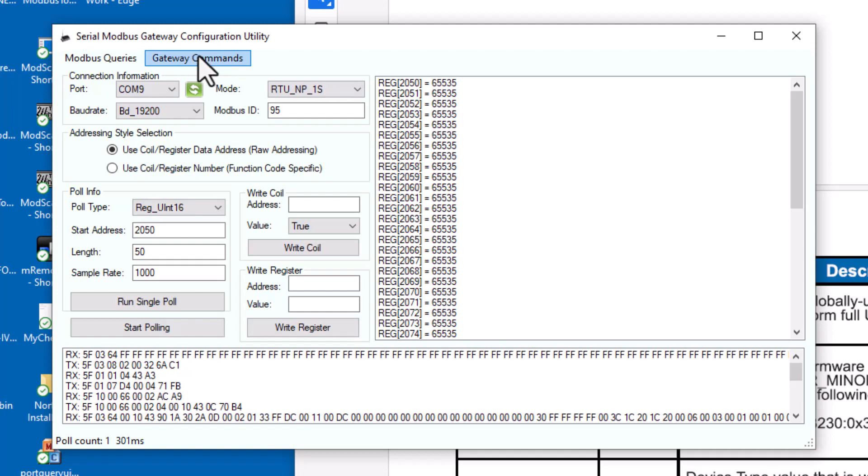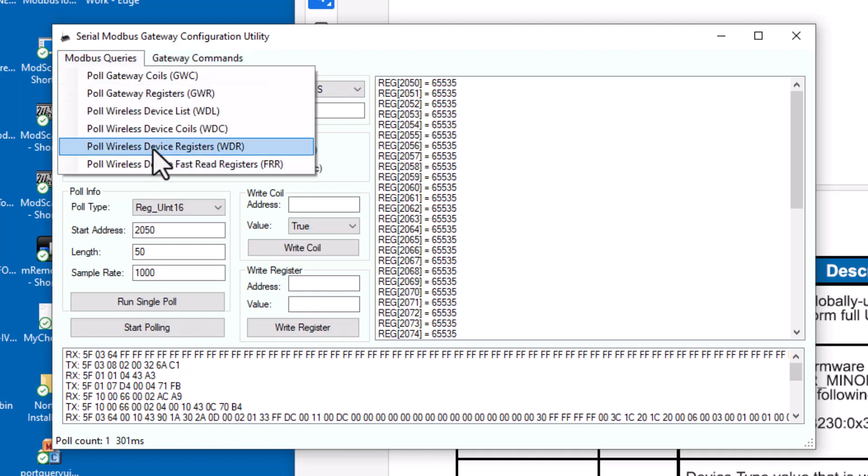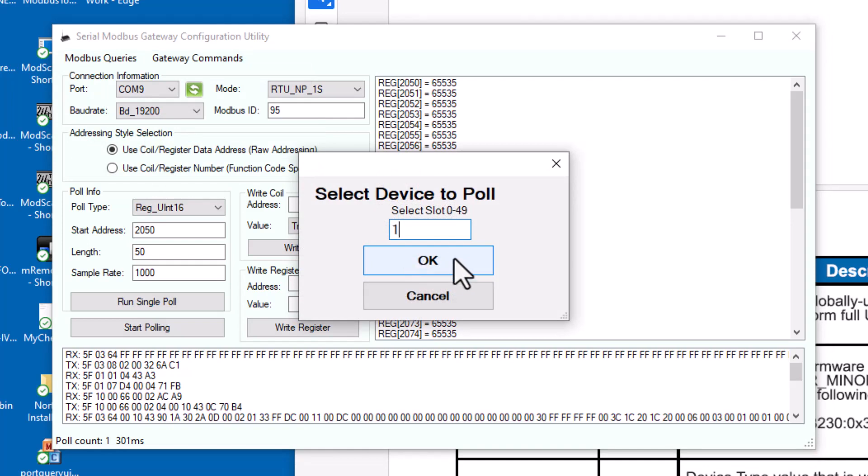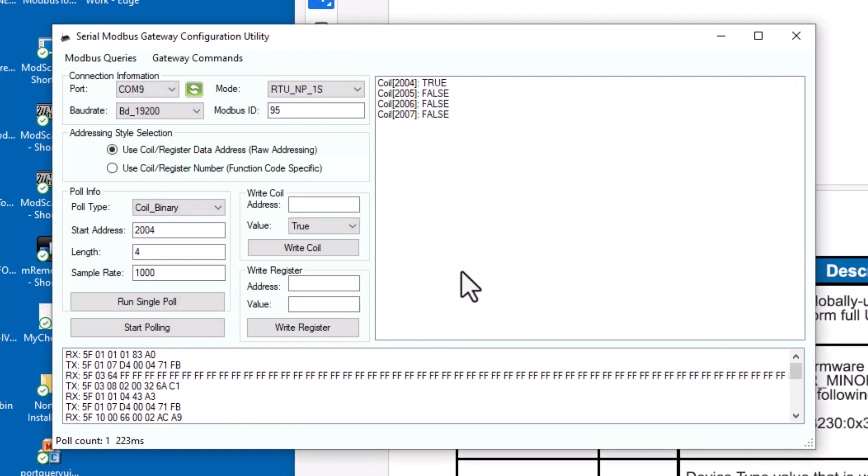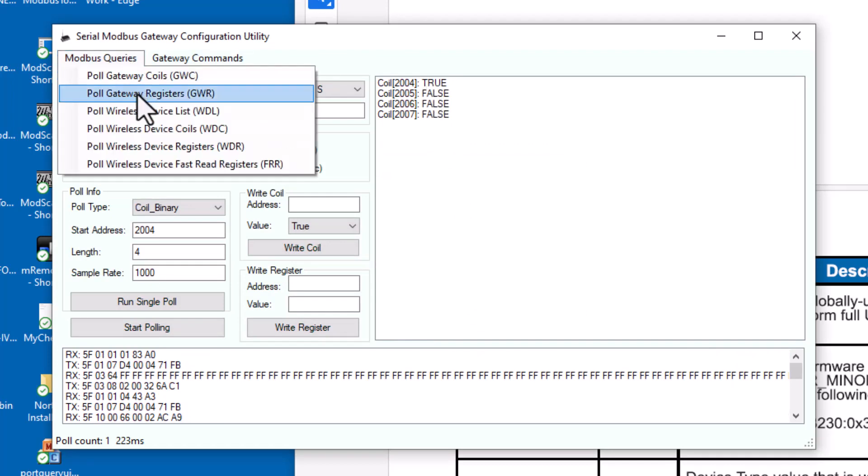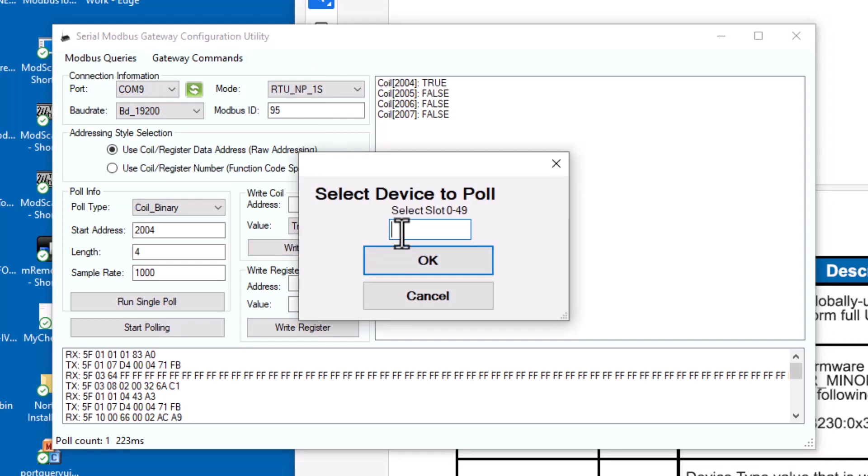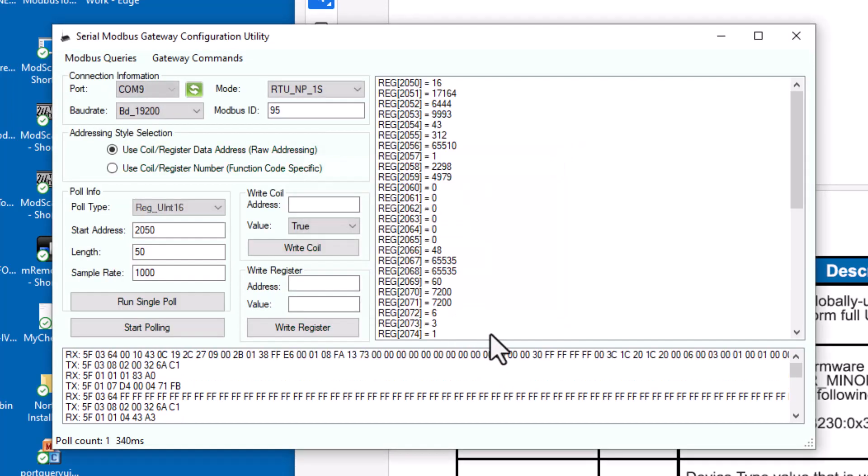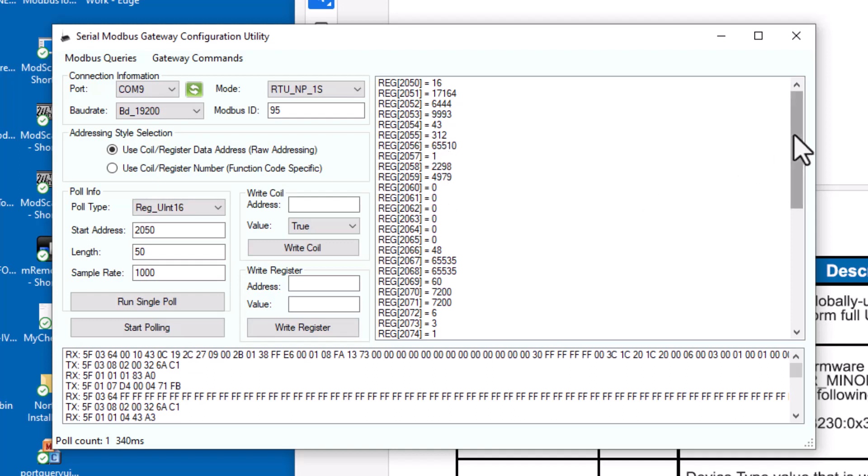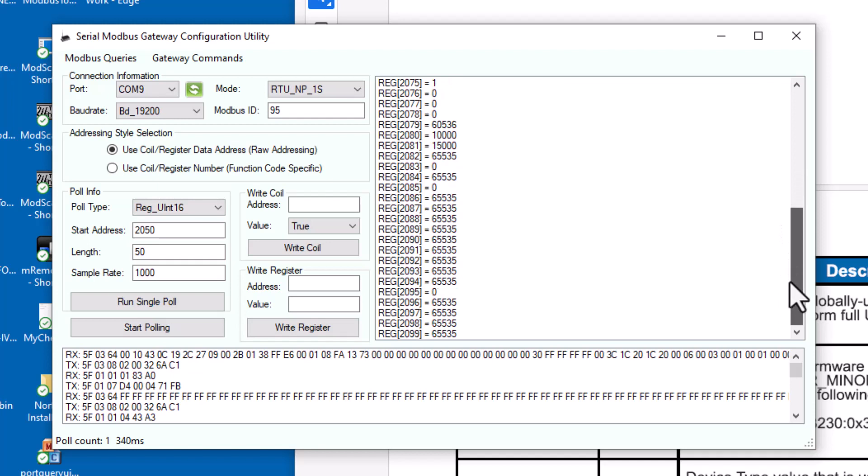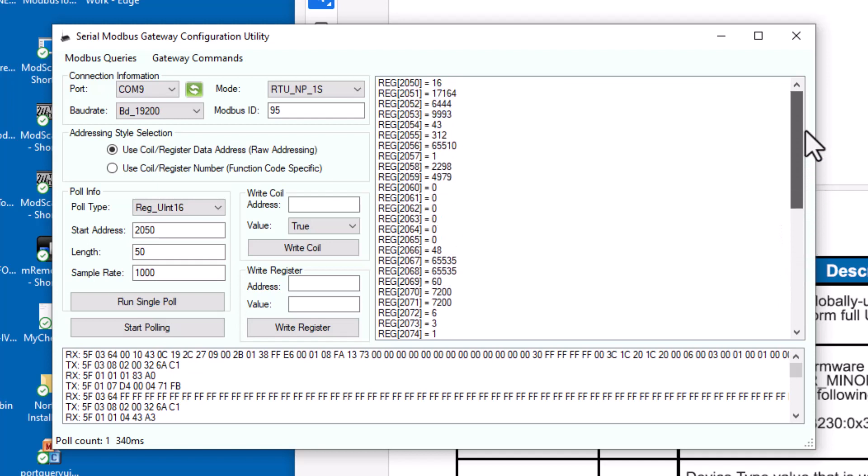All right, we got data returned on that one and we can read the actual sensor data. Here we pop the battery in on the sensor, get that plugged in. Let's try that set of commands again, Wireless Device Coils, one, OK. Perfect, I imagine that's showing if the unit is transmitting or not. If we go back and look at the holding registers or the analog data, first sensor one, perfect, got all of our data points reading through, 3.12 volts.